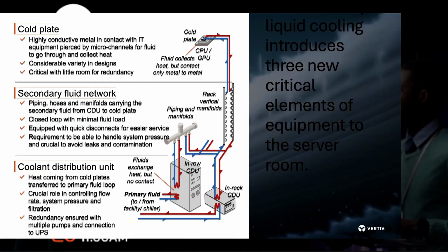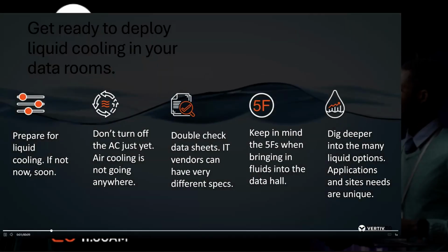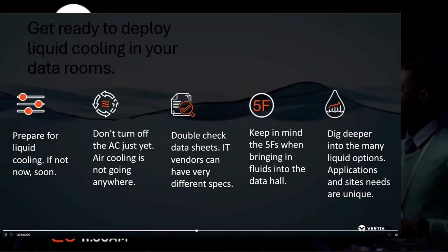With air cooling, fans blow out the heat from the servers and the air takes it out. That's moved away from because of the quantity of heat now generated. You can see your red line and your blue line - your cold plate, your secondary fluid network, your coolant distribution unit sitting outside, that fluid flows right into your cold plates, and then takes the heat, just like sticking a hot rod inside water and expelling the heat almost immediately.